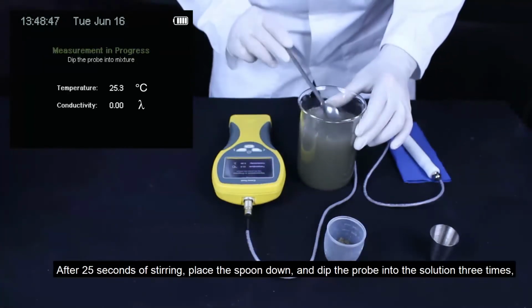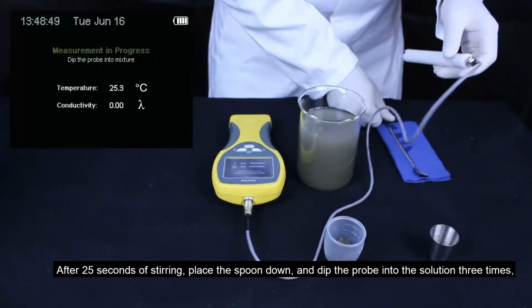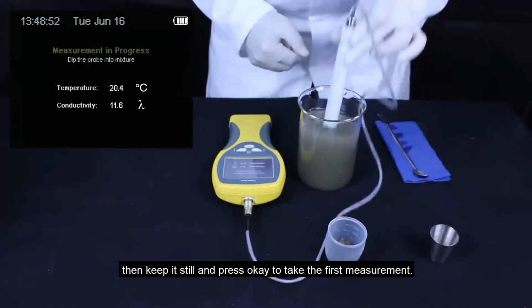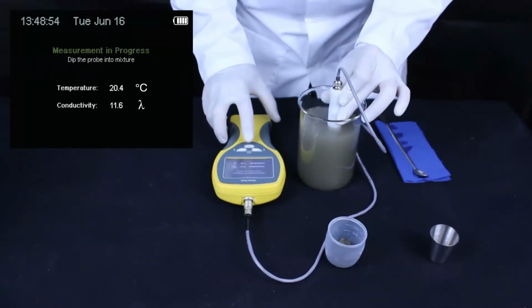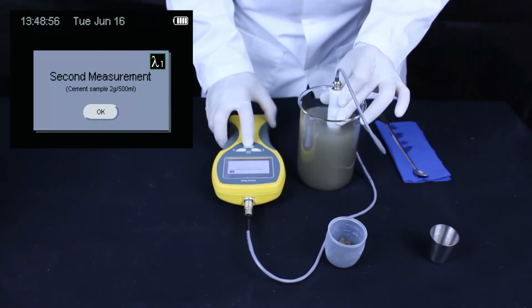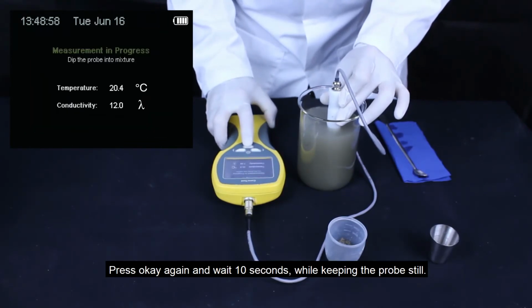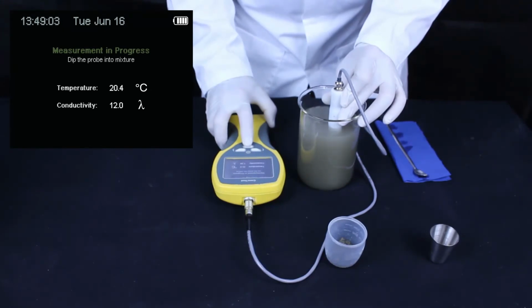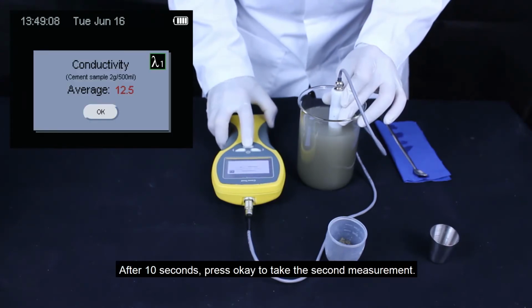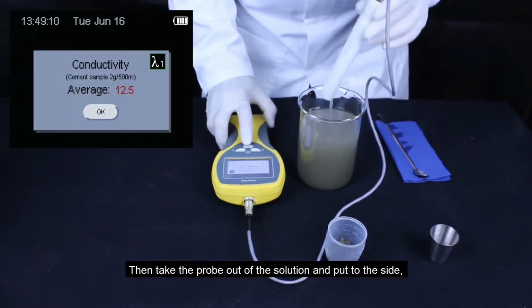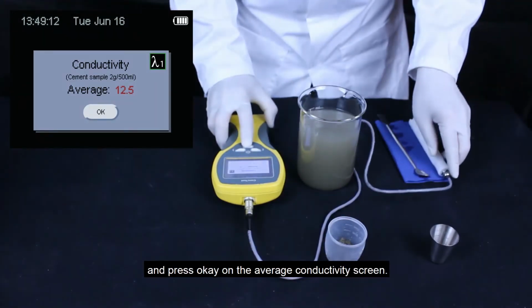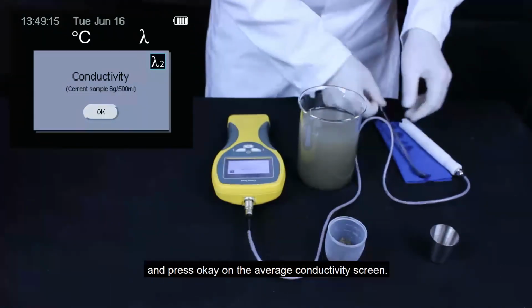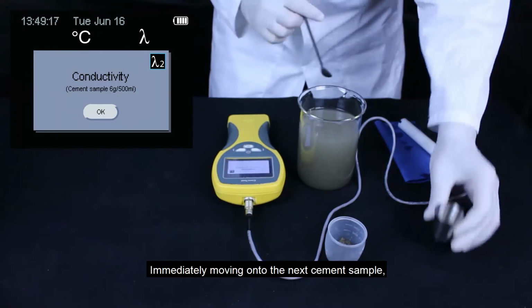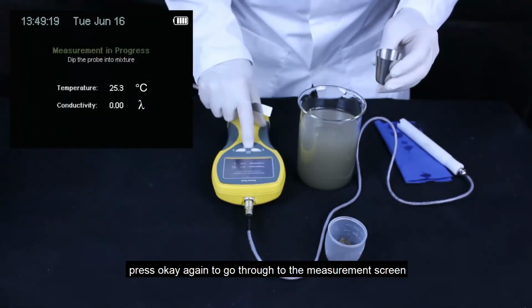After 25 seconds of stirring, place the spoon down and dip the probe into the solution 3 times, then keep it still and press OK to take the first measurement. Press OK again and wait 10 seconds while keeping the probe still. After 10 seconds, press OK to take the second measurement. Then take the probe out of the solution and put it to the side, and press OK on the average conductivity screen. Immediately moving on to the next cement sample, press OK again to go through to the measurement screen.